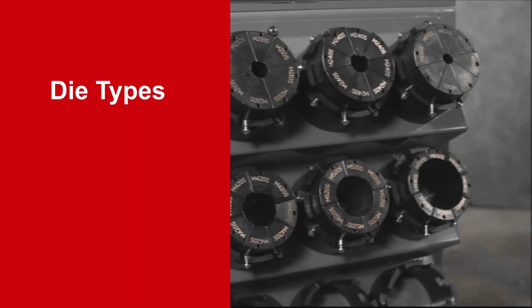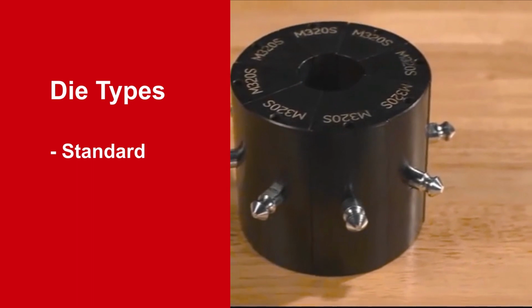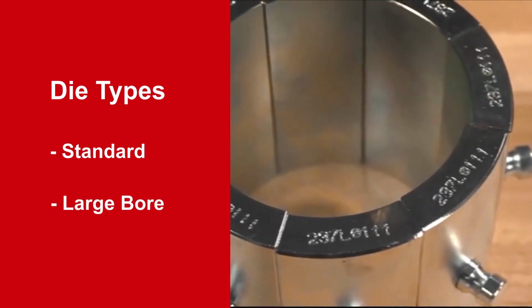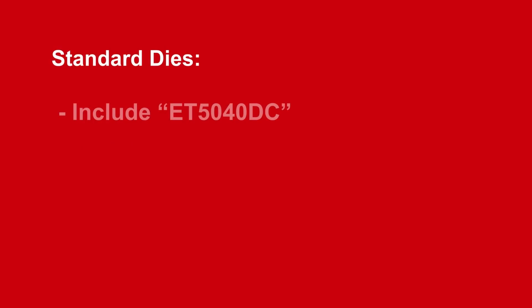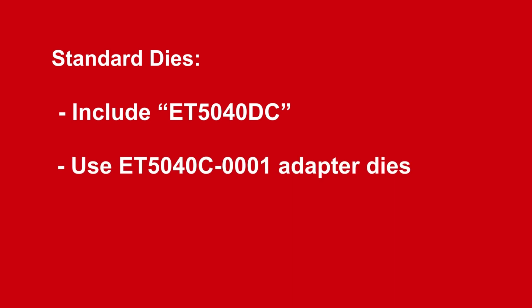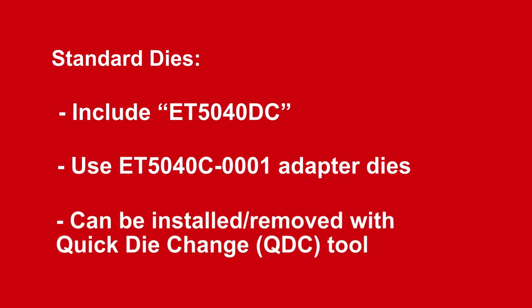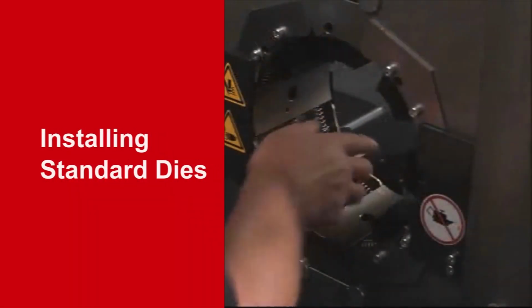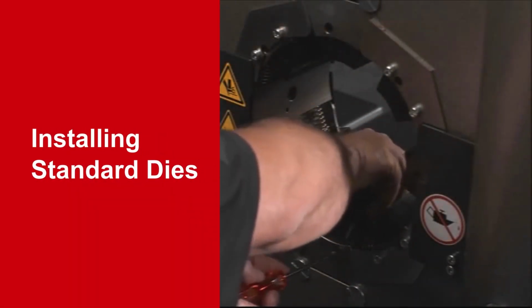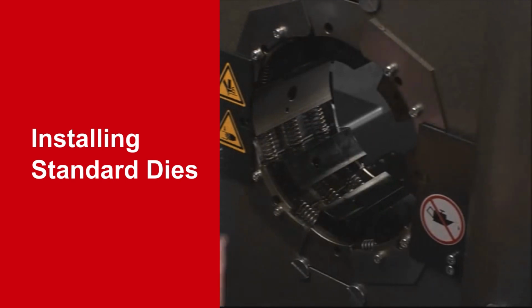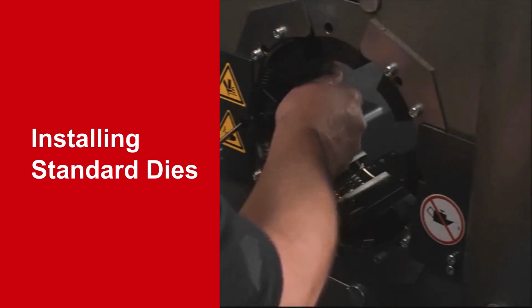The ET5050 shares the same dies as the ET5040 and utilizes two types of dies, standard and large bore. ET5050 standard dies are dies which include ET5040DC in their name string. The standard dies use the ET5040C0001 adapter dies and can be installed and removed with the Quick Die Change or QDC tool. ET5040C0001 adapter die segments should be installed prior to installing any standard bore dies.